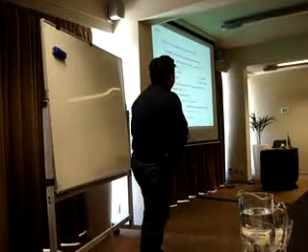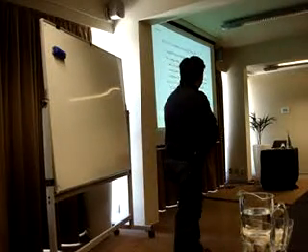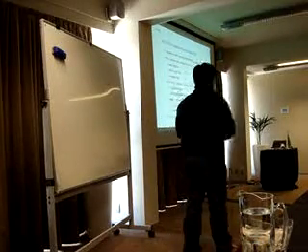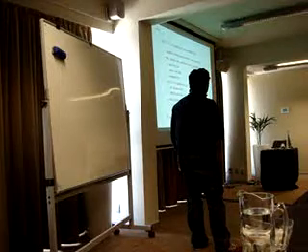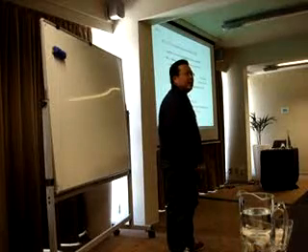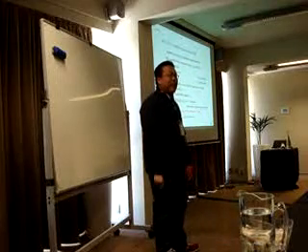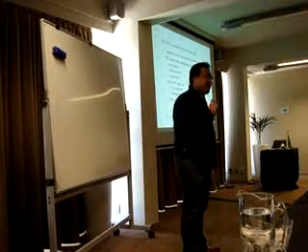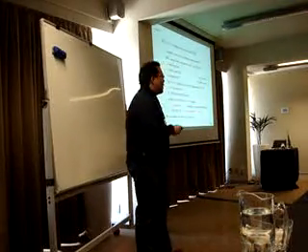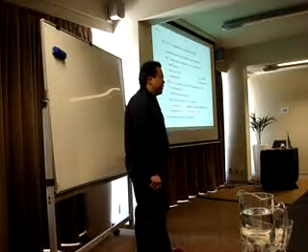What we have achieved is we have formalized and verified about 80% of the standard, and we have found 5 issues. Those issues can be classified as either ambiguities or missing assumptions, or even worse, there are some errors in the implementations. Given that the standard has been used for more than 20 years, they released a new version several months ago, this year or last year. What happened was they removed the whole function block library that we tried to examine, but some errors are still there. They just haven't fixed them.